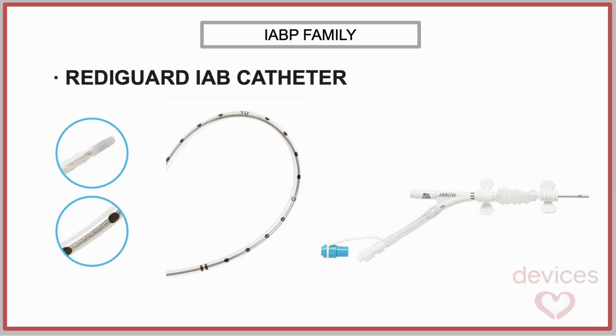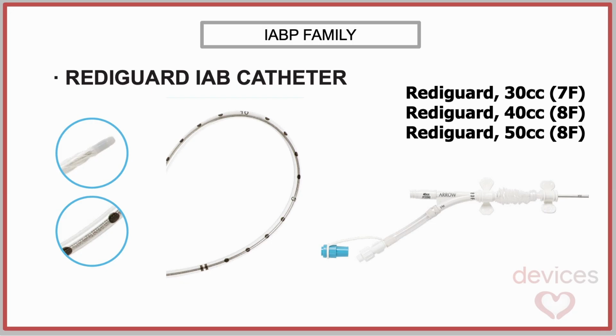The Rediguard catheter is designed to minimize vascular access complications while maintaining excellent hemodynamic performance. Its low-profile design allows the 30 milliliters model to be introduced through a 7 French sheath, making it one of the smallest intra-aortic balloon catheters available. The 40 milliliters and 50 milliliters models are also available, with an 8 French catheter shaft, providing greater balloon volume. A distinctive feature of the Rediguard catheter is its braided stainless steel central lumen, which enhances shaft stability, improves torque transmission, and increases resistance to kinking without compromising flexibility.